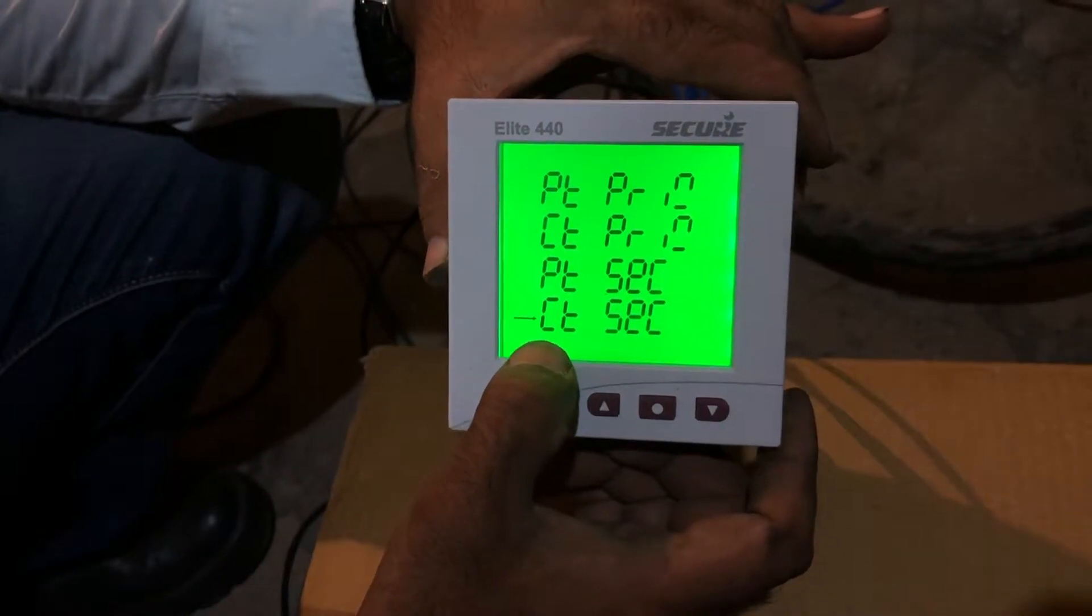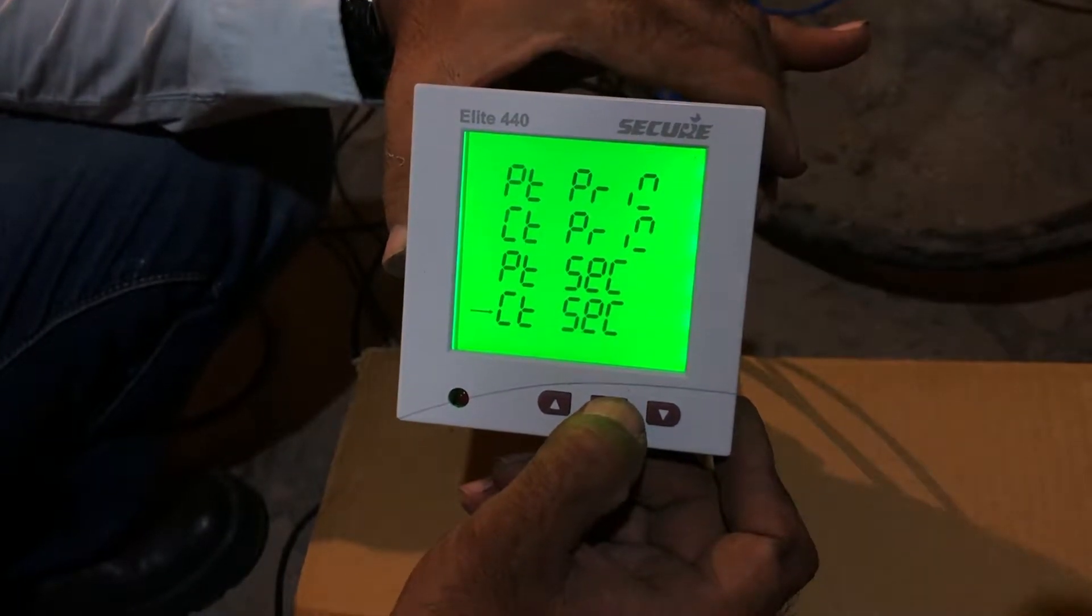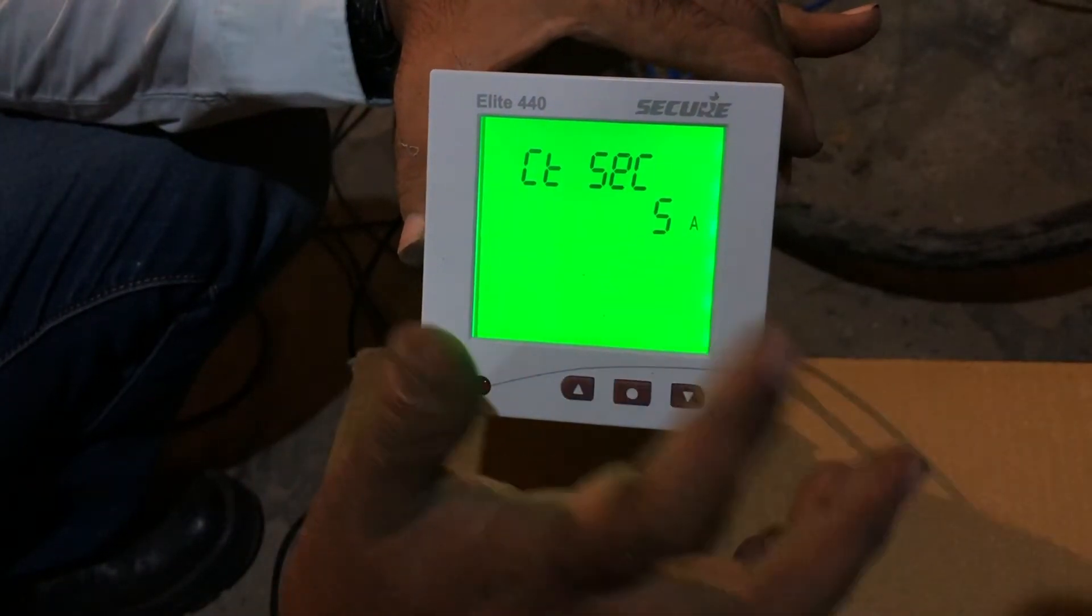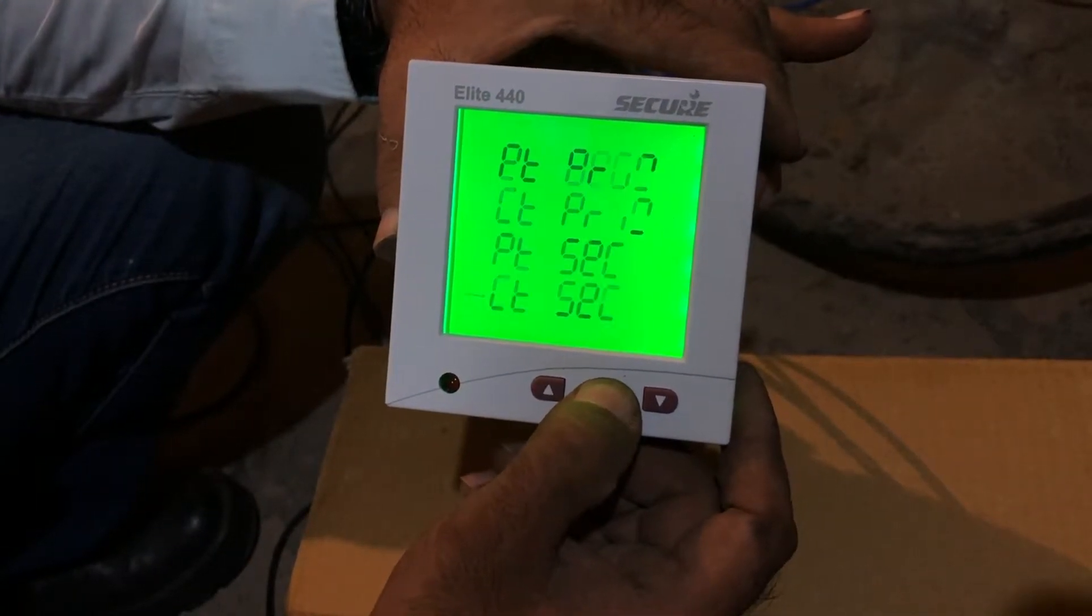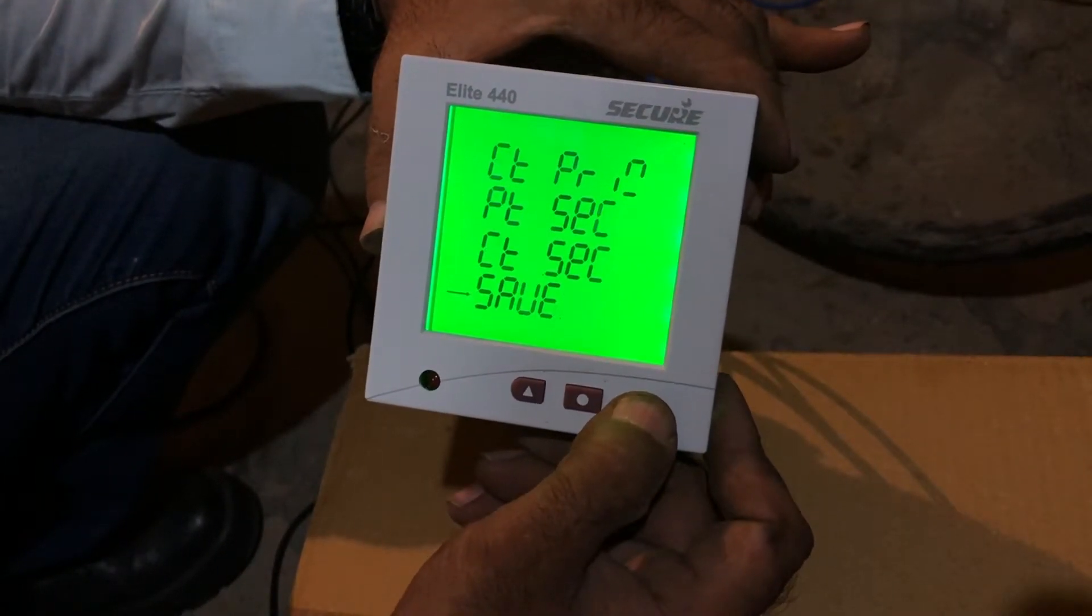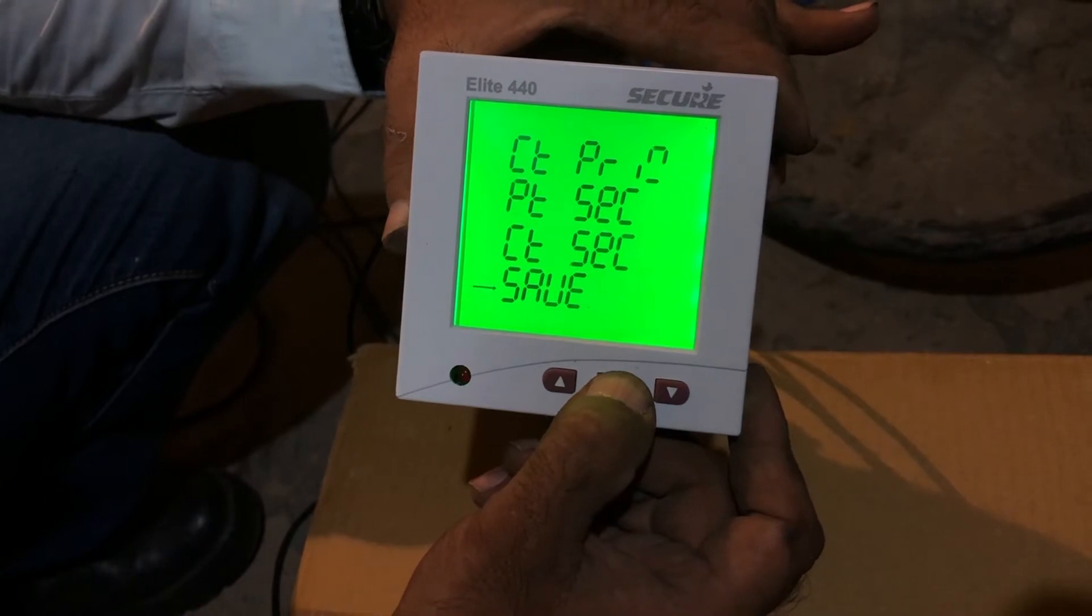Which says CT secondary in the menu. We'll press enter and put the desired value which is 5 ampere in our case. We again press enter and move on to save the settings.